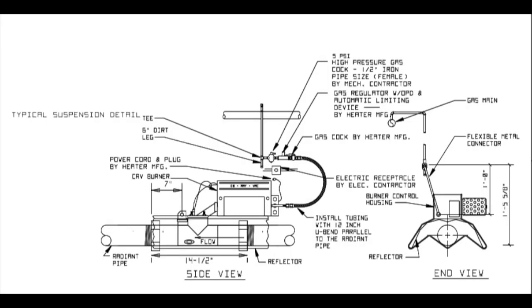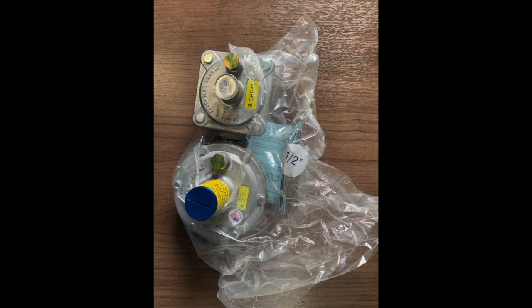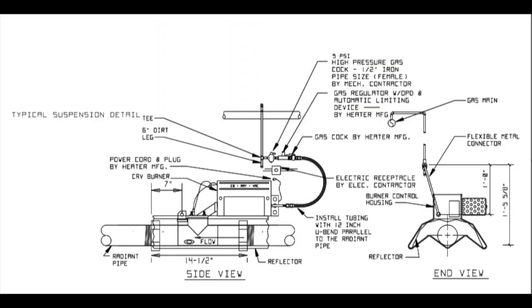The gas piping at the burners must be as the detail shows, no exceptions. The gas flex must be in the shape of a C. The reason for this is the expansion and contraction of the system. The flex must work evenly. If elevated line pressure in the shop, 2 or 5 psi, regulators will be supplied. These regulators are installed as shown and will not require a vent.